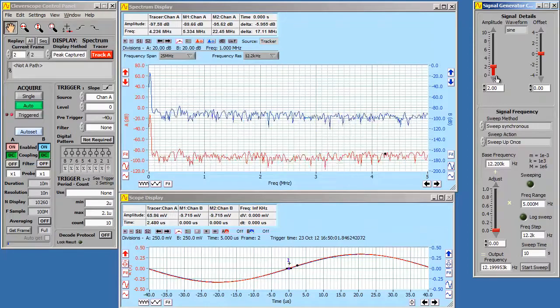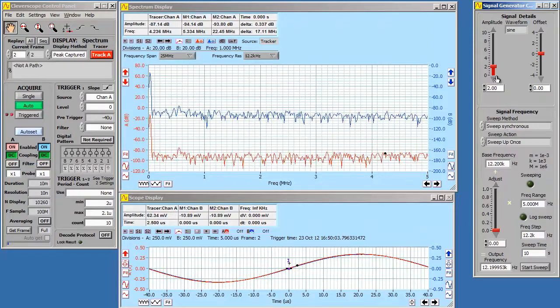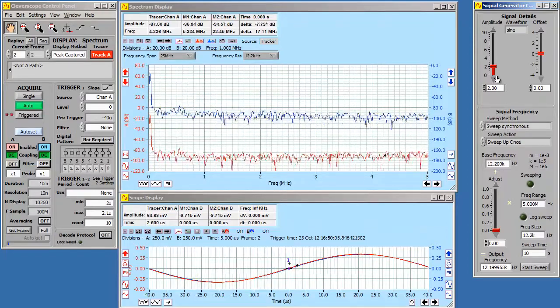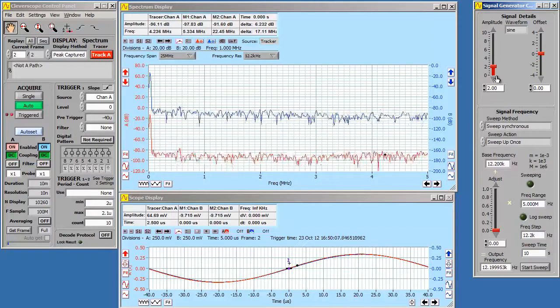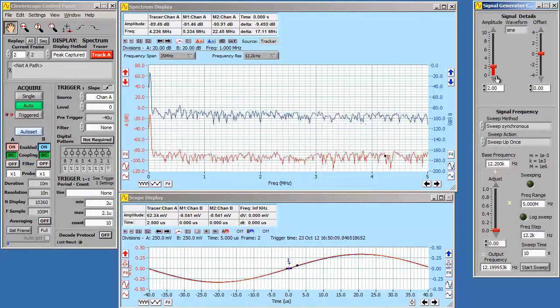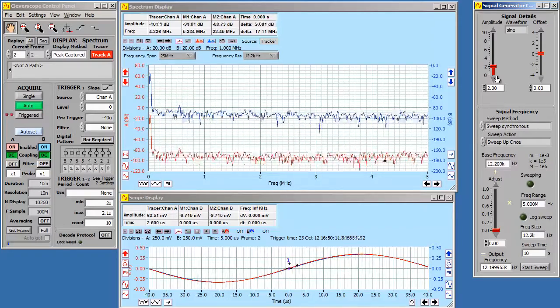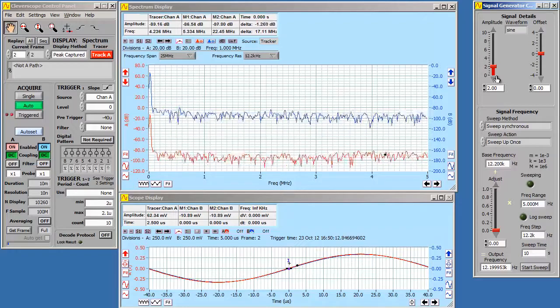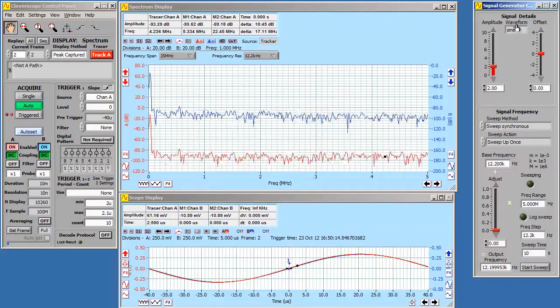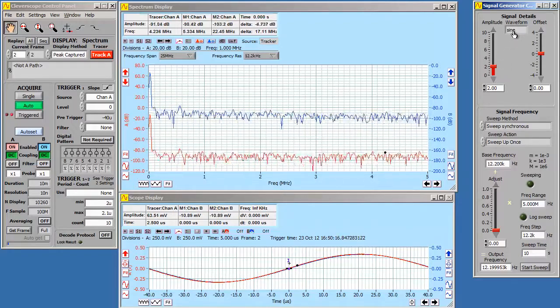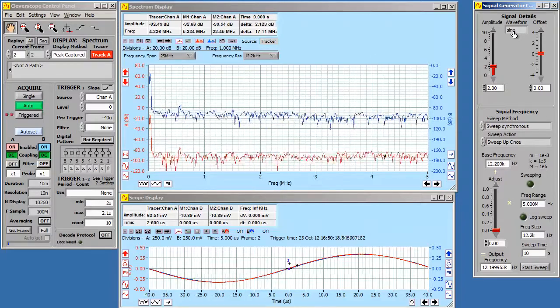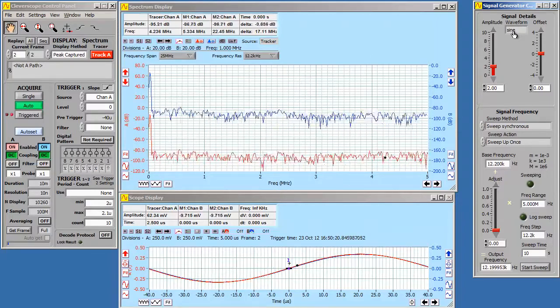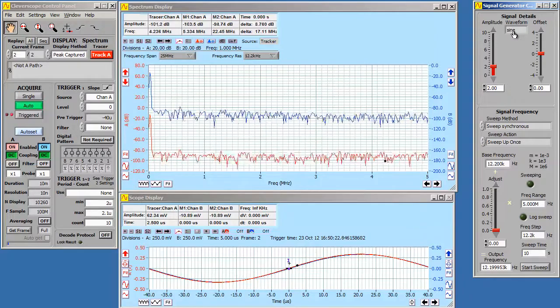An output amplitude of 2 volts is pretty good as a trade off between distortion and signal to noise ratio. So we'll stay with 2 volts. We also want a sine wave because we just want to sweep a single frequency over the frequency range. Okay that's all set up.